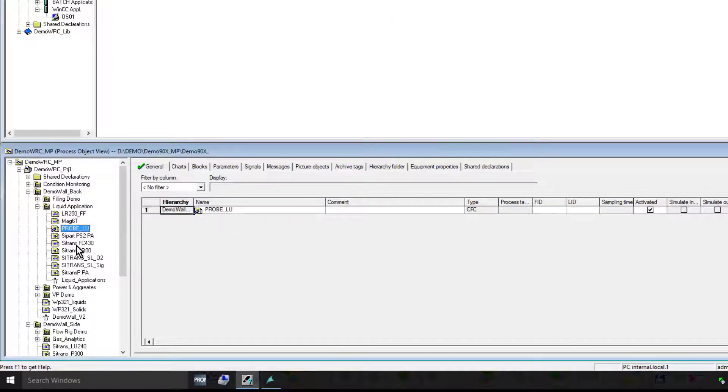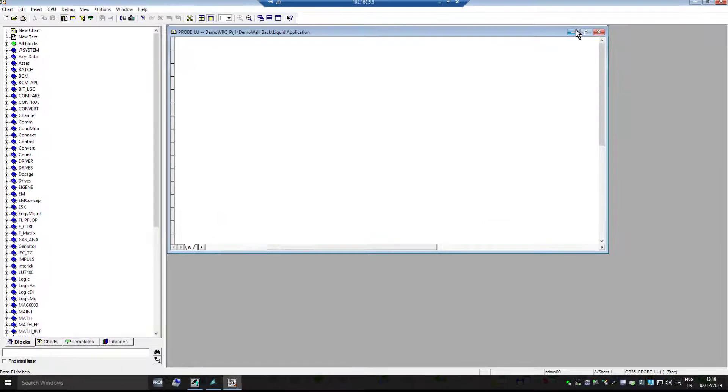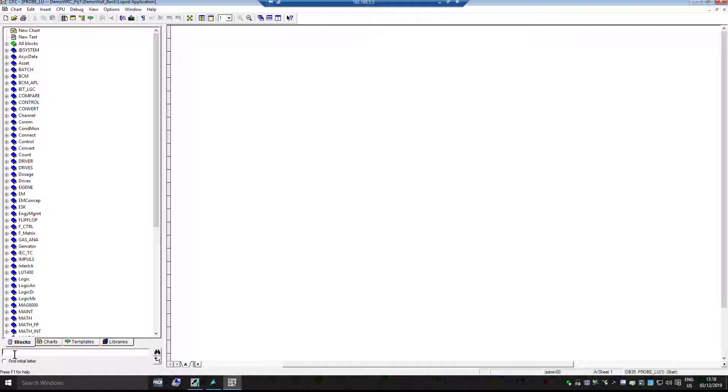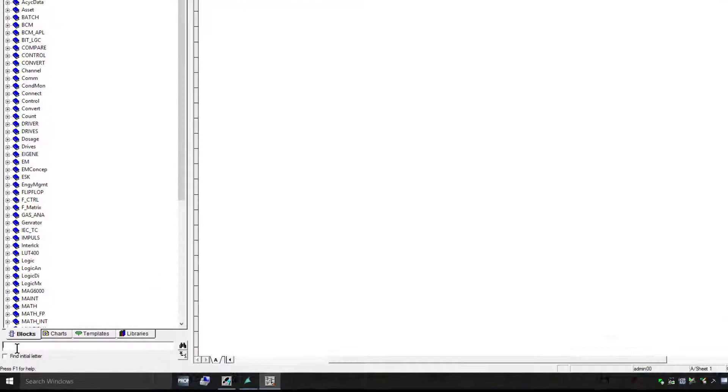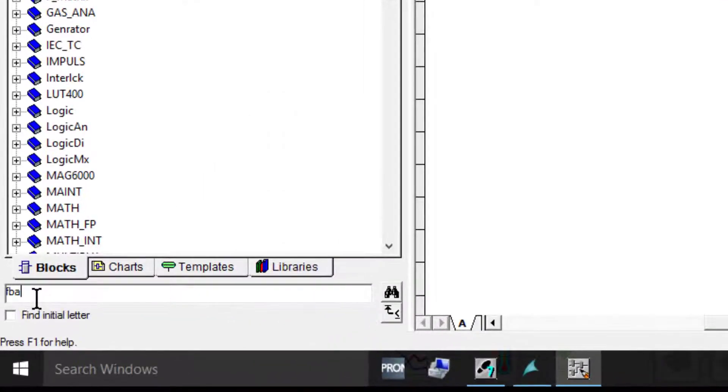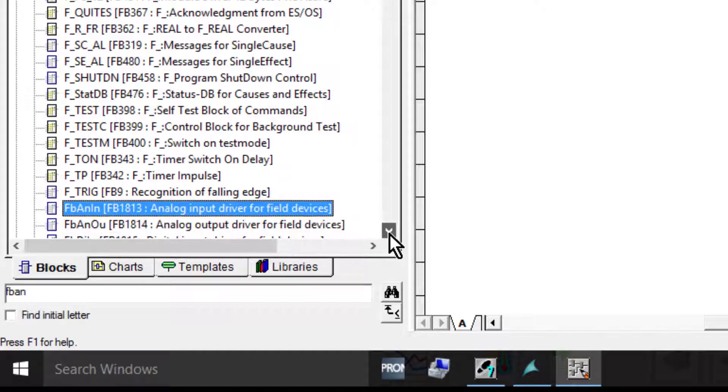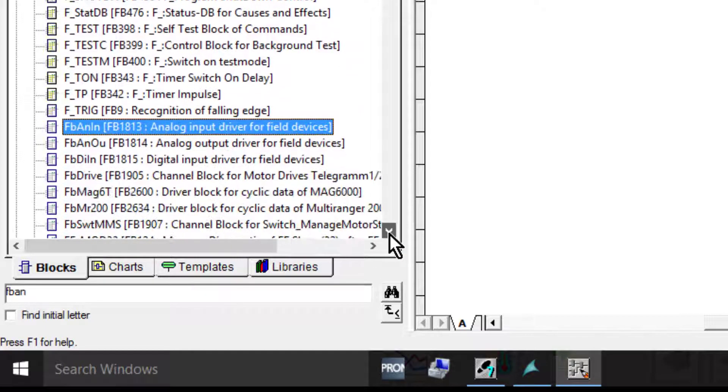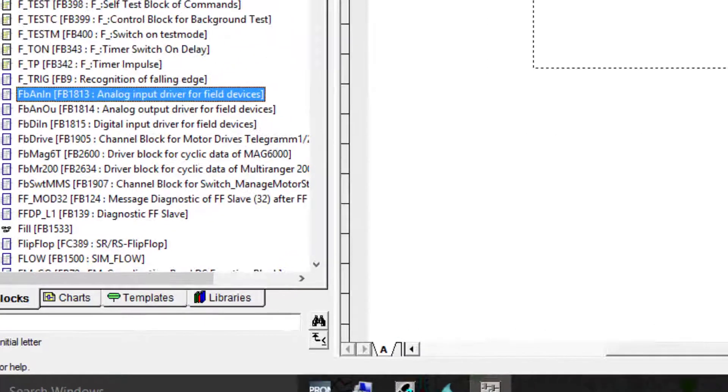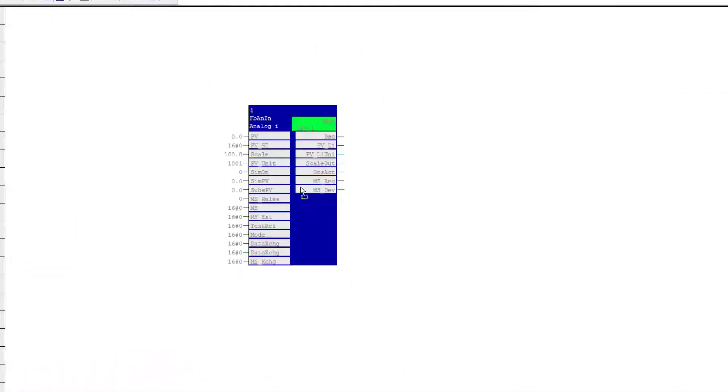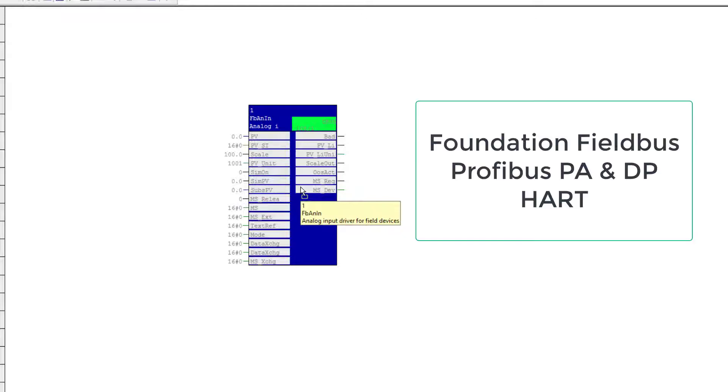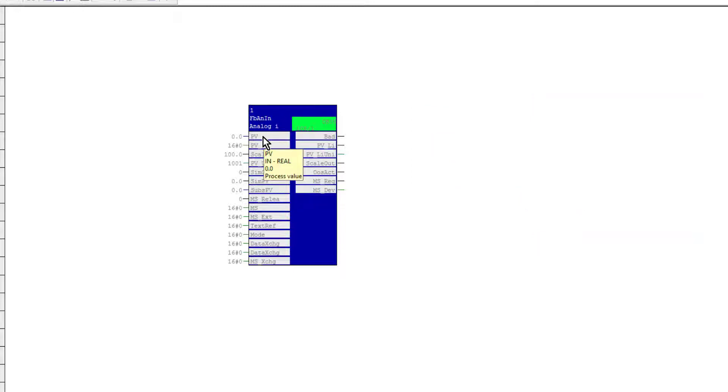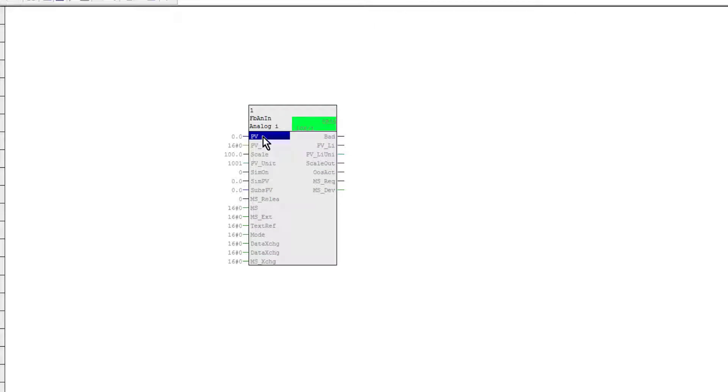Then I'll go and insert that. Now here's your libraries - there's a few analog blocks that you can use. We're in, it's an FB ANA IN, so I can search on that. FB analog input. FB will take in communication, so what do we mean by that? This block will work with Foundation Fieldbus, Profibus DP, Profibus PA, and HART devices, so I have to make the interconnection.